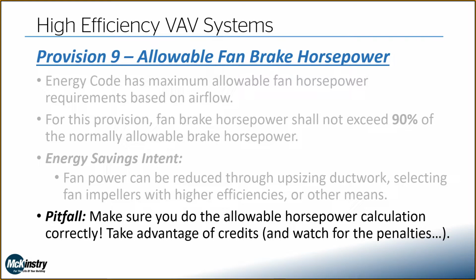The main issue is usually that we're not taking advantage of credits. If you have a system with a high efficiency filter, for example, you are actually allowed more horsepower because that filter has more pressure drop than a standard filter. But there are also some penalties. There are things that will penalize you, where they say we're not going to give you as much because of X, Y, or Z with that system. So knowing how to do that calculation can save you a lot of headache, especially in making sure you're taking advantage of any applicable credits that are going to help you.